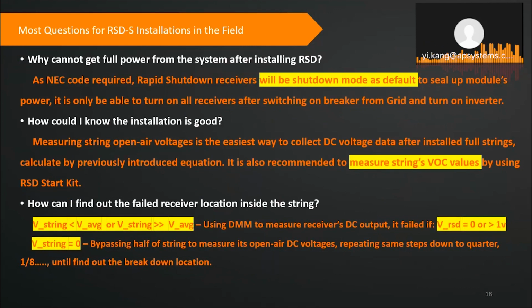How could I know the installation is good? The best way is to measure their VOC values using the start kit, or just using the DMM to measure the open-air voltage on the DC home run to get the value and calculate it by the safety voltage. Another question is, how could I find out the failed receiver location inside of the string? That's very tricky. They have a different way. Later on, I'm going to introduce more detail.